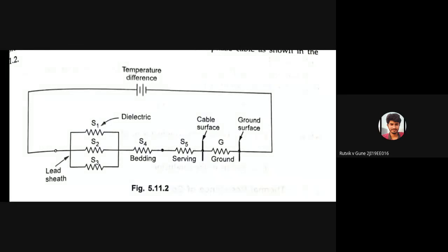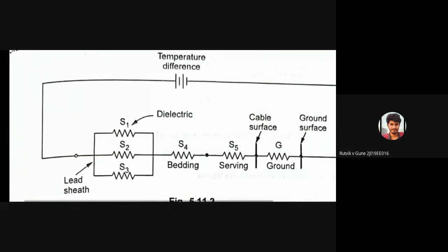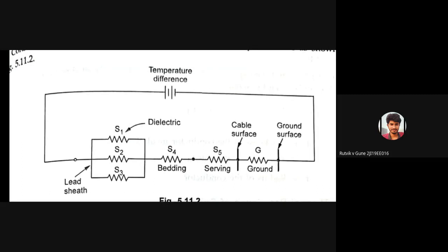In the equivalent circuit, capital S1, S2, S3, S4, and S5 are all thermal resistances. Temperature difference is represented in the form of a battery. S1, S2, S3 are the thermal resistances of the three dielectric parts in parallel; S4 is the thermal resistance of the bedding; S5 is the thermal resistance of the serving; and G is the thermal resistance of the ground.